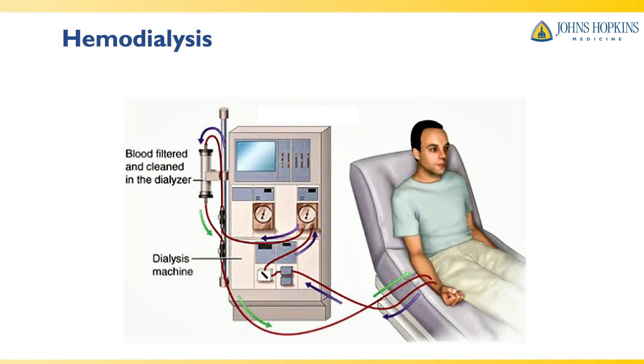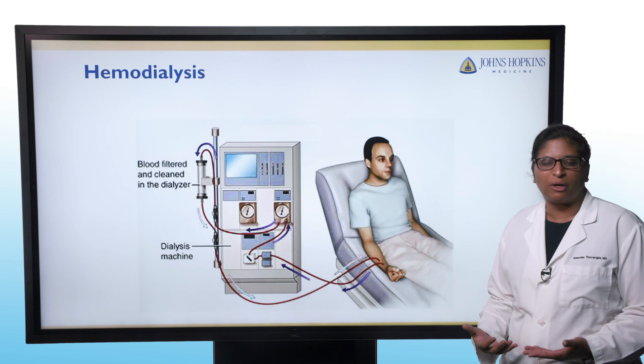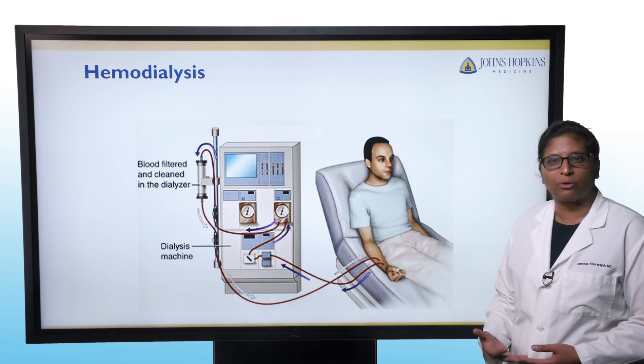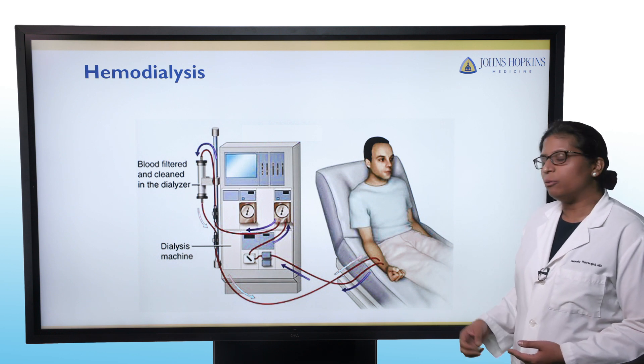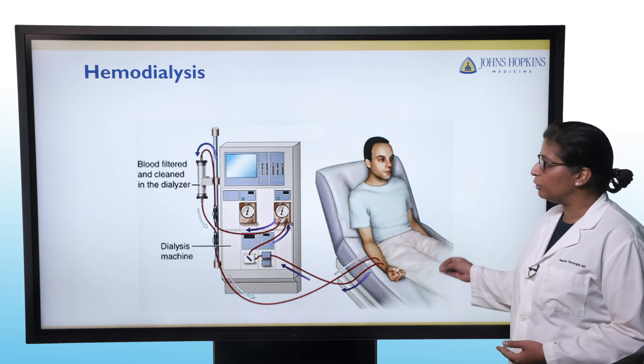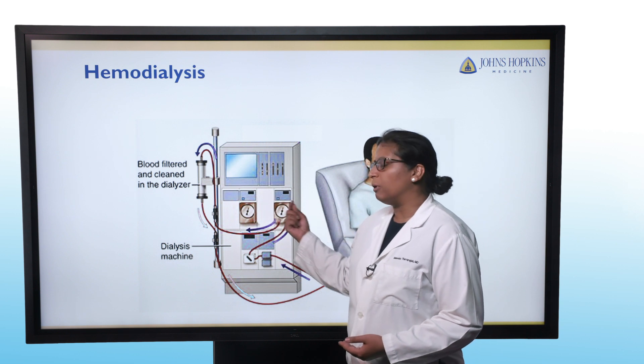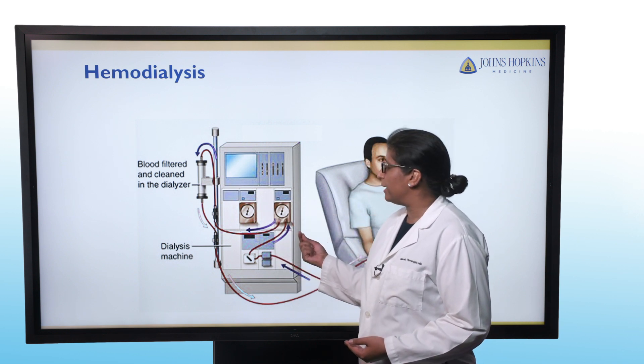This picture demonstrates the basic setup of hemodialysis. The principle is that there's some way of getting blood from the individual — remember, our kidneys were cleaning our blood throughout the day, overall cleaning about 180 to 200 liters of blood. During a dialysis treatment, we get the blood from the individual, run it through a machine and through what we call an artificial kidney, or dialyzer, and the cleaned blood is then returned back to the patient.